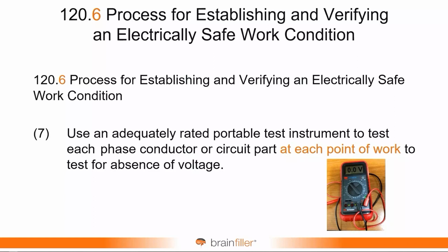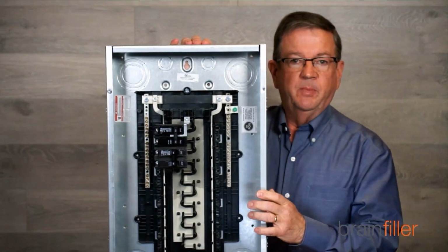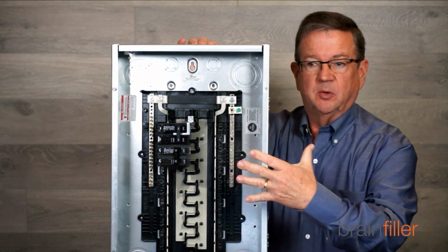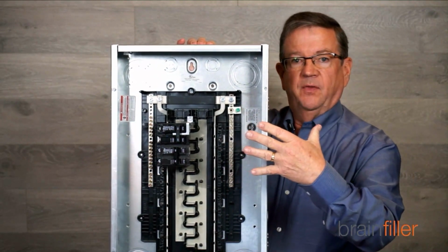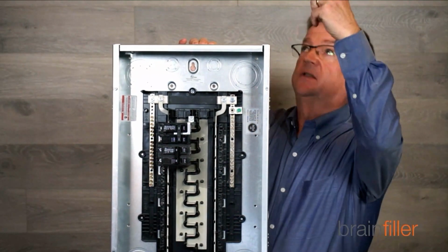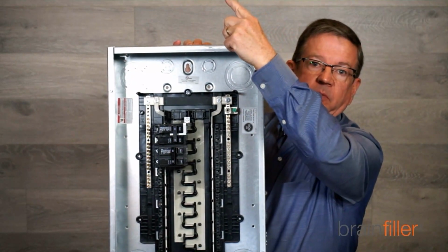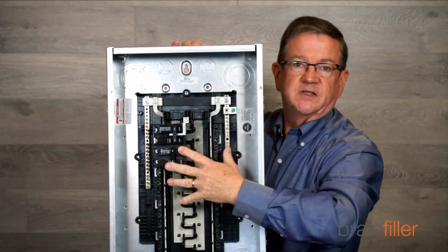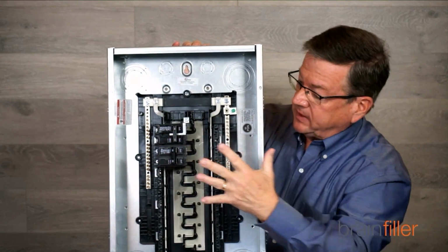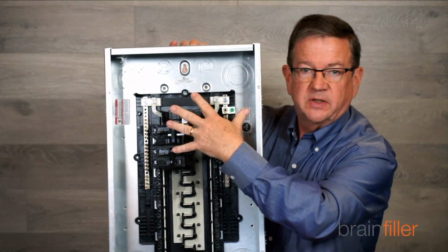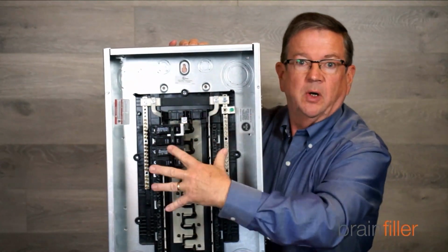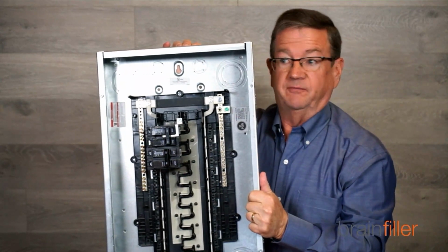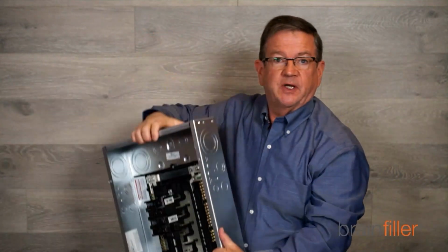At each point of work. The intent of this was to make sure that if you're going to be conducting work on, let's say, this particular panel right here, then you don't test what's upstream to test for absence of voltage. You test locally. So it just simply means, okay, you're going to be working here. This is going to be electrically safe. Test at the point of work to make sure that it's electrically safe. It's very simple. But it was a clarification that was helpful, that was needed.